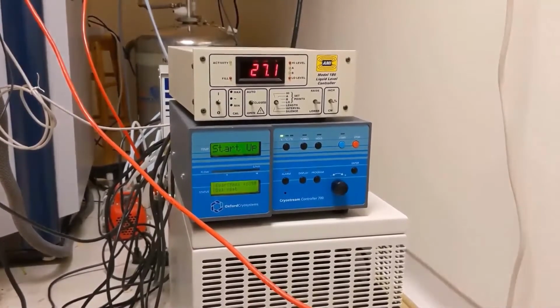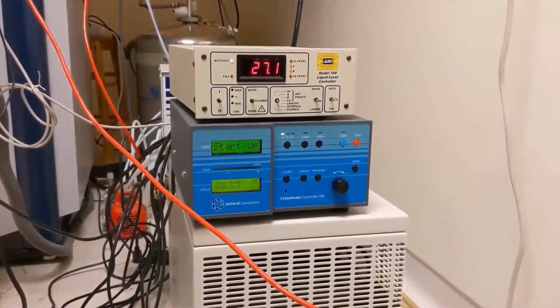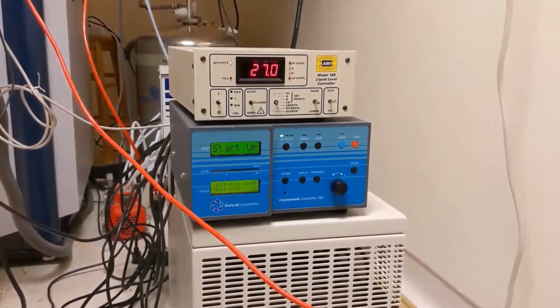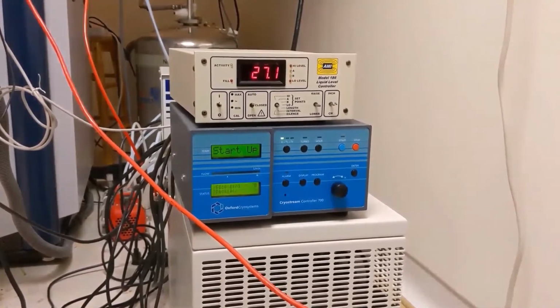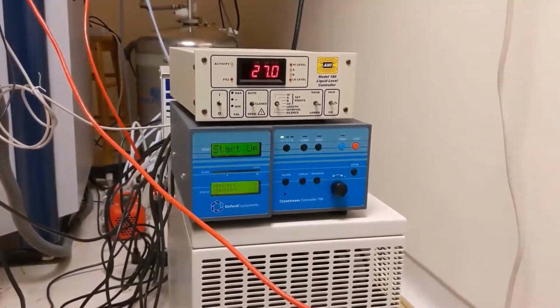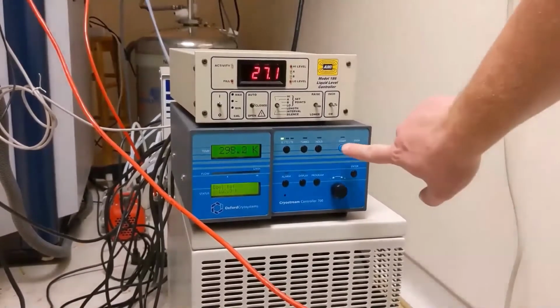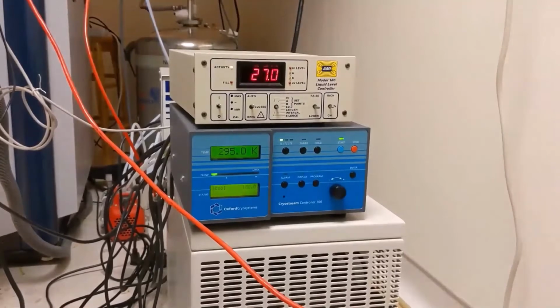First, press the blue start button one time. The screen now says startup, and the bottom status screen will go through a startup procedure. This takes about 15 seconds. Once the status window says cool to 100K, the cryostream is ready. Press the blue start button one more time to begin cooling.